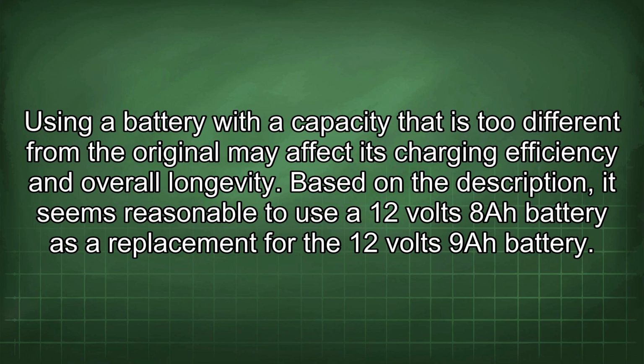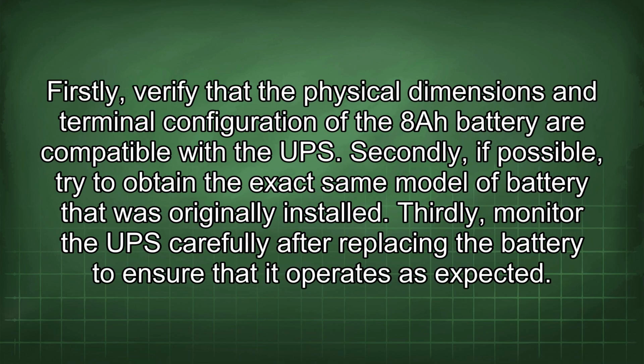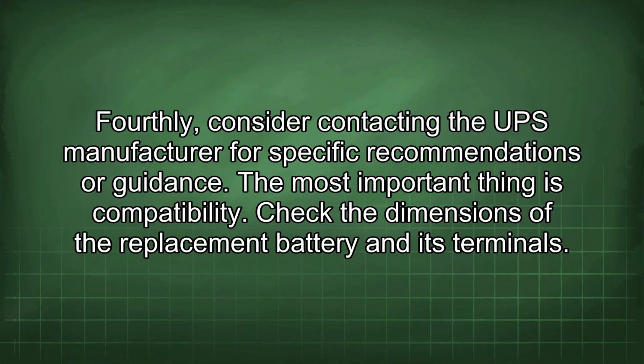longevity. Based on the description, it seems reasonable to use a 12 volts 8 Ah battery as a replacement for the 12 volts 9 Ah battery. Firstly, verify that the physical dimensions and terminal configuration of the 8 Ah battery are compatible with the UPS. Secondly, if possible, try to obtain the exact same model of battery that was originally installed. Thirdly, monitor the UPS carefully after replacing the battery to ensure that it operates as expected. Fourthly, consider contacting the UPS manufacturer for specific recommendations or guidance.